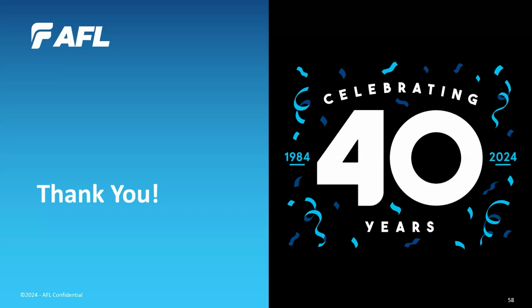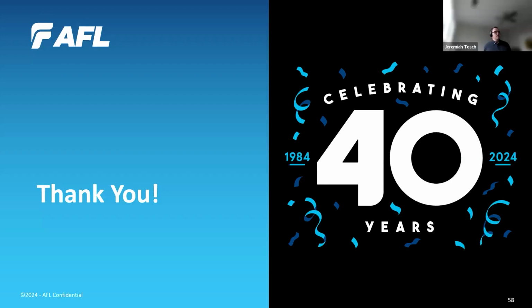Can you discuss the challenges of multi-mode and single-mode fiber OPGW and how to handle that conversion? Do you mean splicing them together, or just the differences? She didn't indicate, so no worries. They're typically not splice compatible. There are different versions of single mode that can be spliced together, but single mode and multi-mode aren't splice compatible. Single mode is the typical option for OPGW, but we do see multi-mode occasionally. The issue with multi-mode in optical ground wire is it's only suited for very short distance transmission, so it can't really be used in long distance applications like OPGW typically requires, but we do see it occasionally.